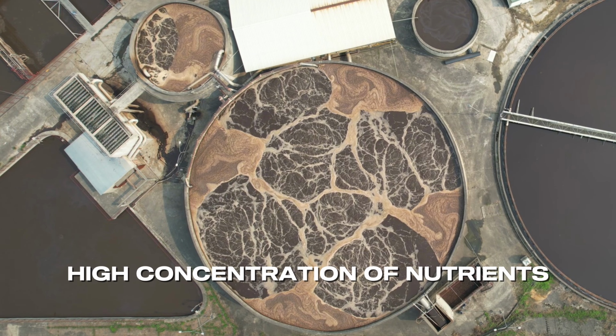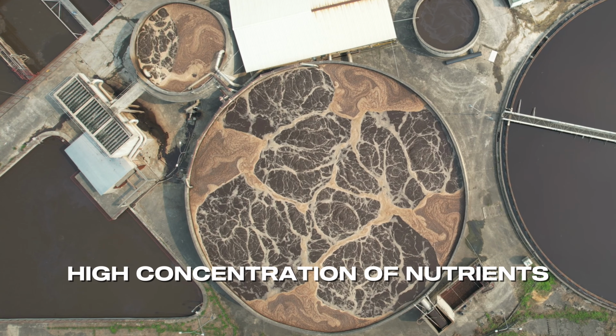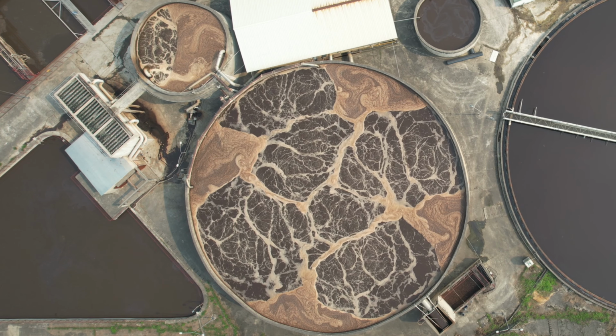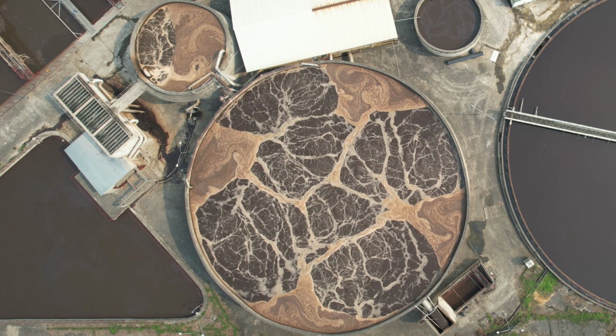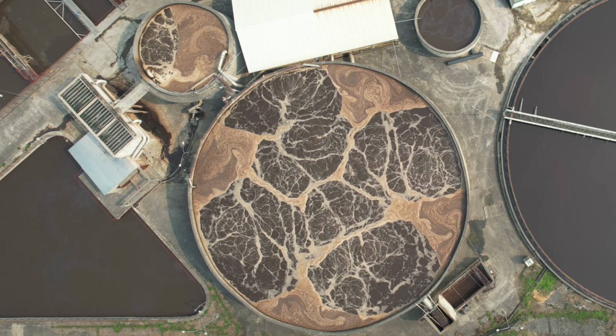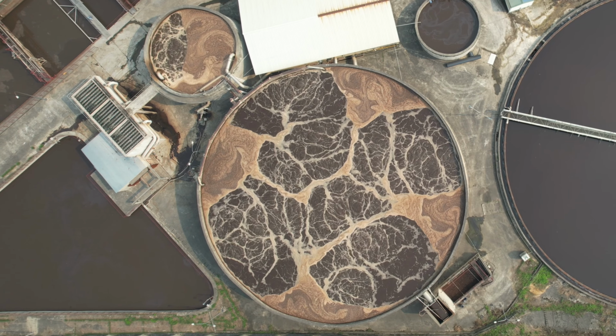High concentrations of nutrients such as nitrogen and phosphorus, or toxins like solvents, cleaners, and industrial additives, can act as inhibitors, poisoning the biomass and bringing the entire process to a halt. Having a full inventory of chemicals used on site is essential to spotting these threats before they hit the reactor.